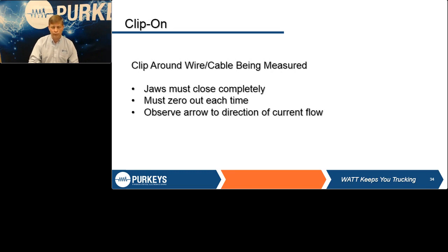The other thing is you want to make sure you test a cable away from any other circuits, because again, it is picking up that magnetic field. If you had a big bundle of wires and didn't separate the one wire from the others, you could pick up the negative field from the other ones, or even more from another circuit in parallel, and you could maybe even double what the readings are. So be very careful and separate that wire from the rest of the circuits.